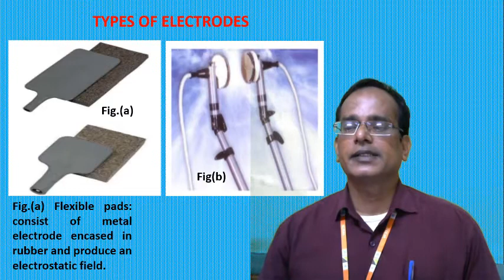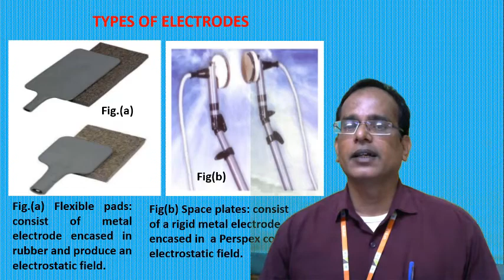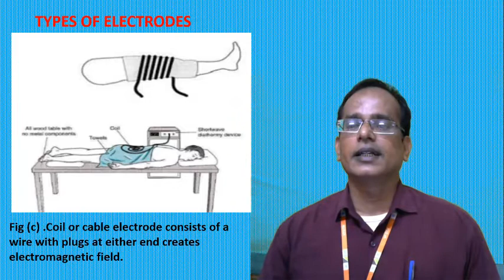Next one is called air space plates. The second, figure B, shows air space plates. It consists of rigid metal electrodes encased in a perspex cover which produces the electrostatic field. So this is the second type of electrode. Now we are going to see the third type of electrode. The name is coil type, or another name is cable electrode. It consists of a wire with a plug at either end and creates an electromagnetic field. So this comes under inductive field diathermy.